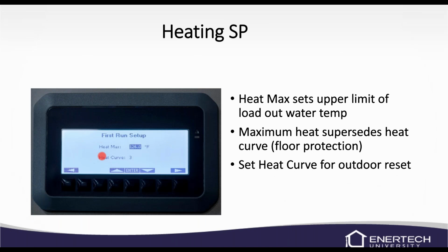You'll next go to your heating set point. The heat max sets the upper limit of the load out water. So if you want the max that water ever leaves that unit at 90, you could put it at 90. No matter what the heat curve tells you, the heat max will always supersede it, whether it's higher or lower. The heat max is there for floor protection. So if you've got expensive Brazilian hardwood floors or something, then you can set that temperature a lot lower.